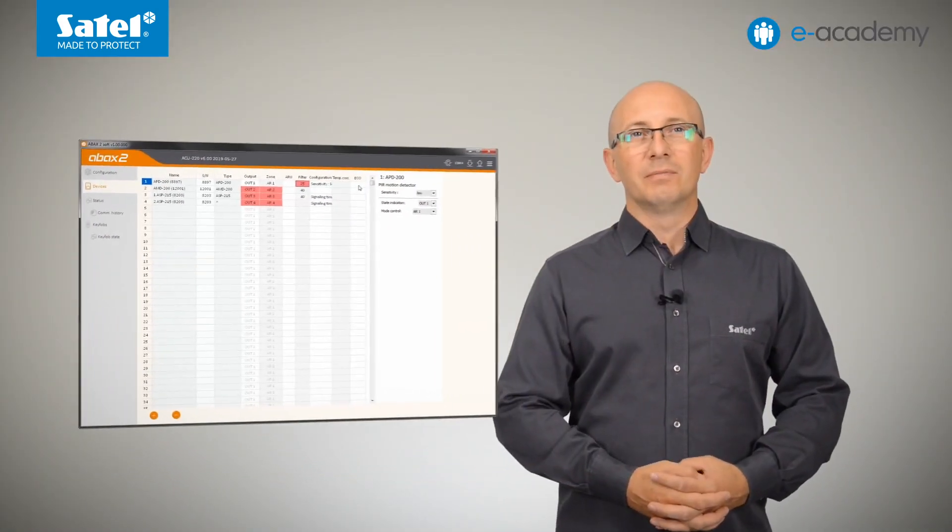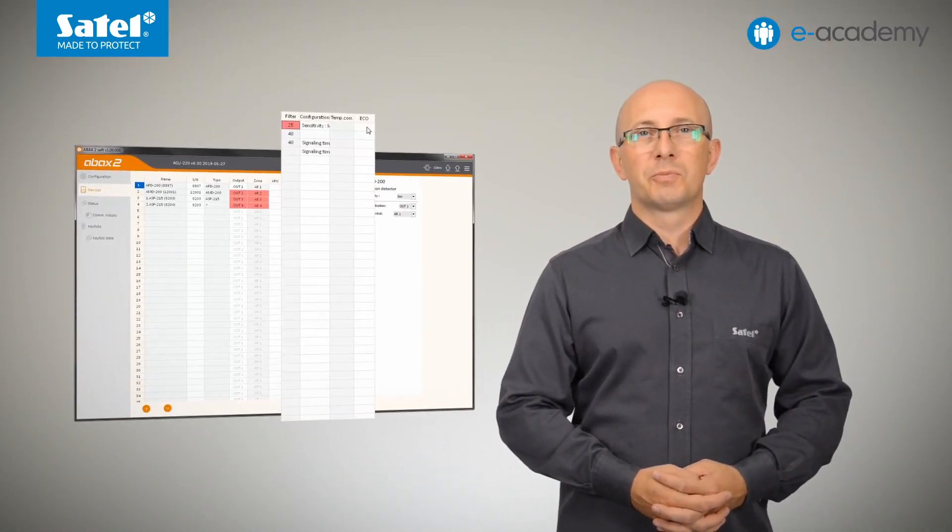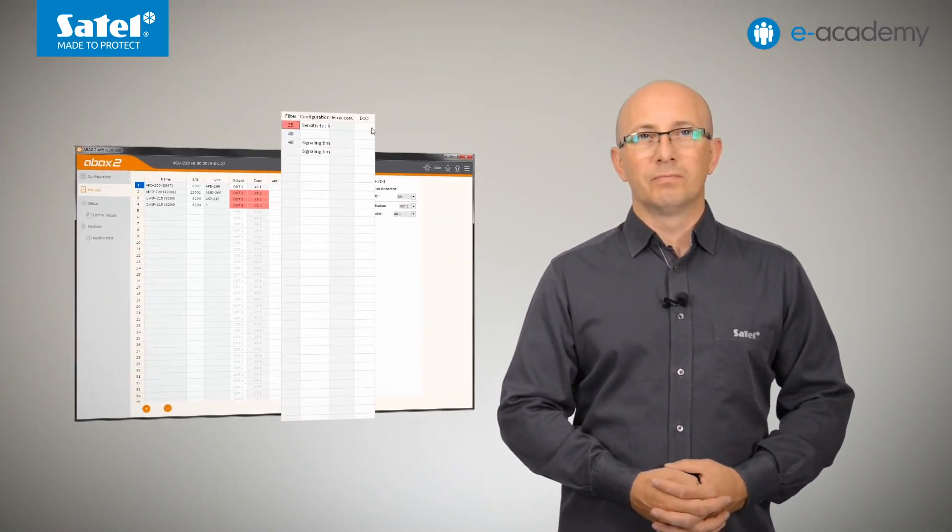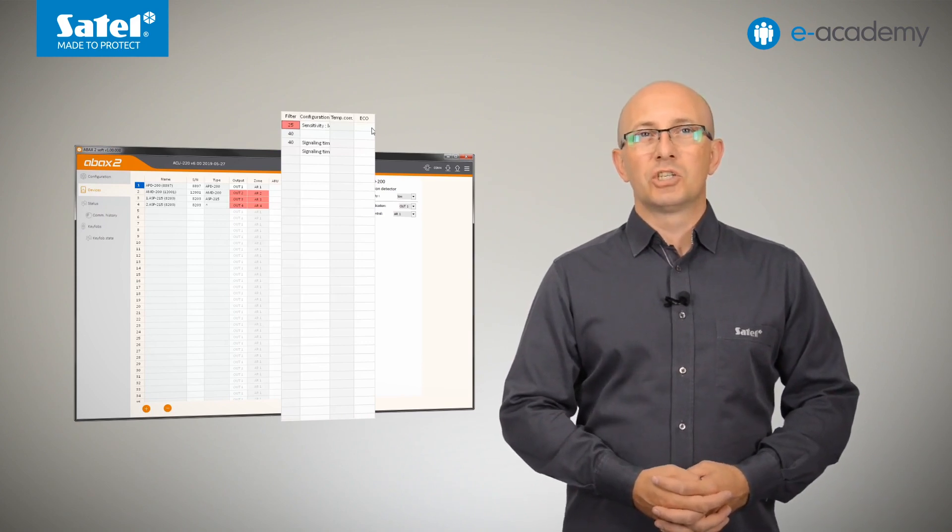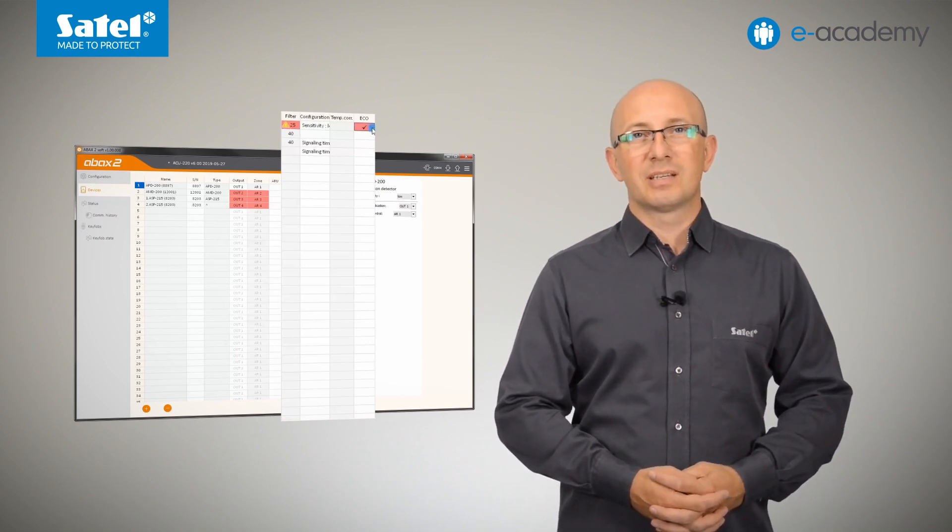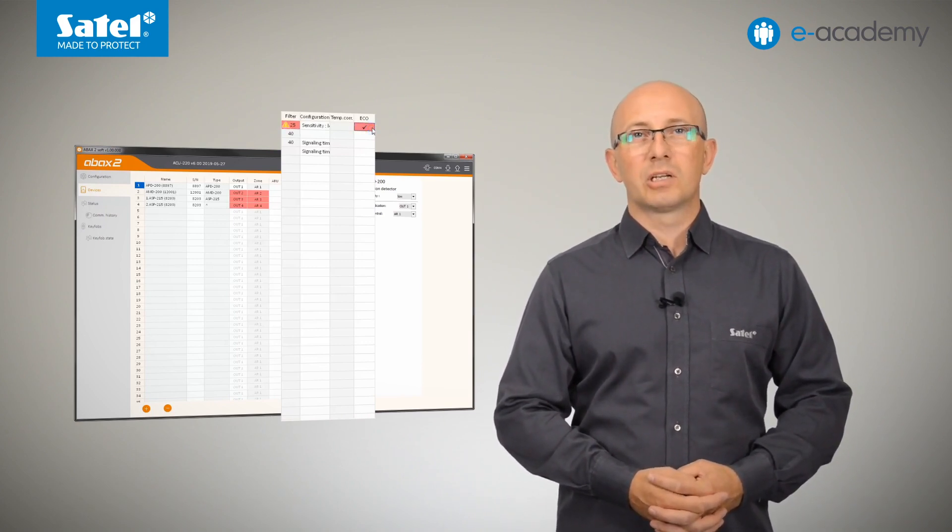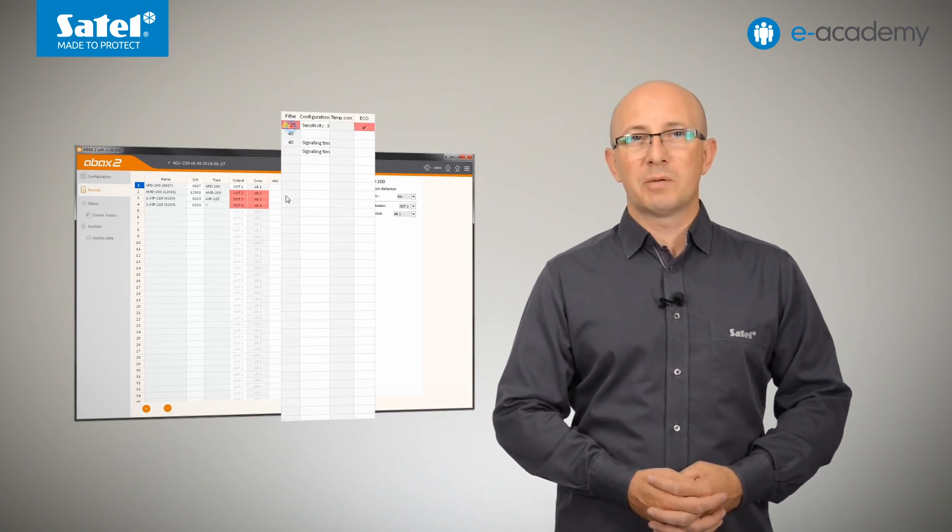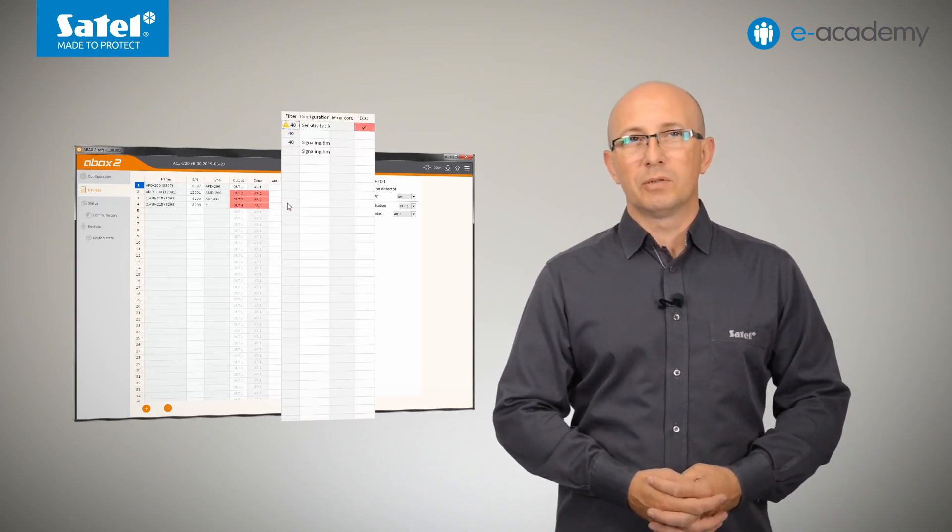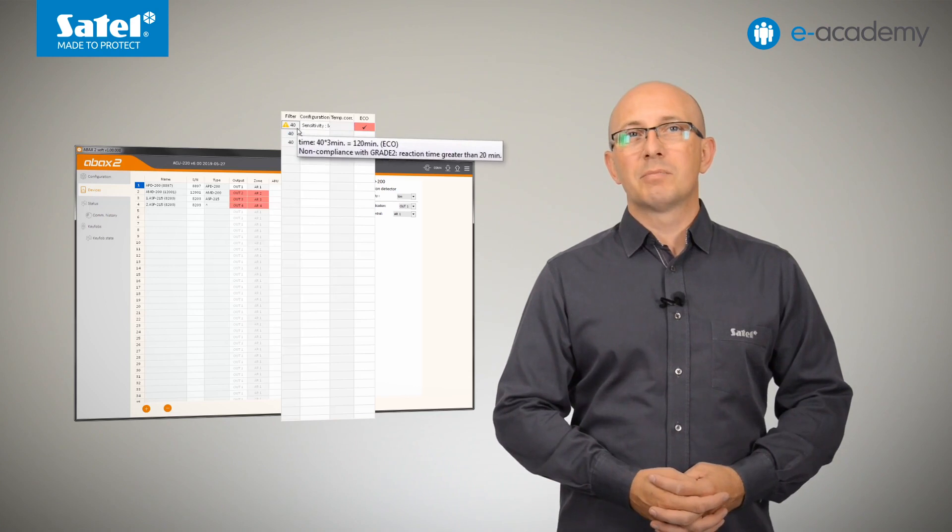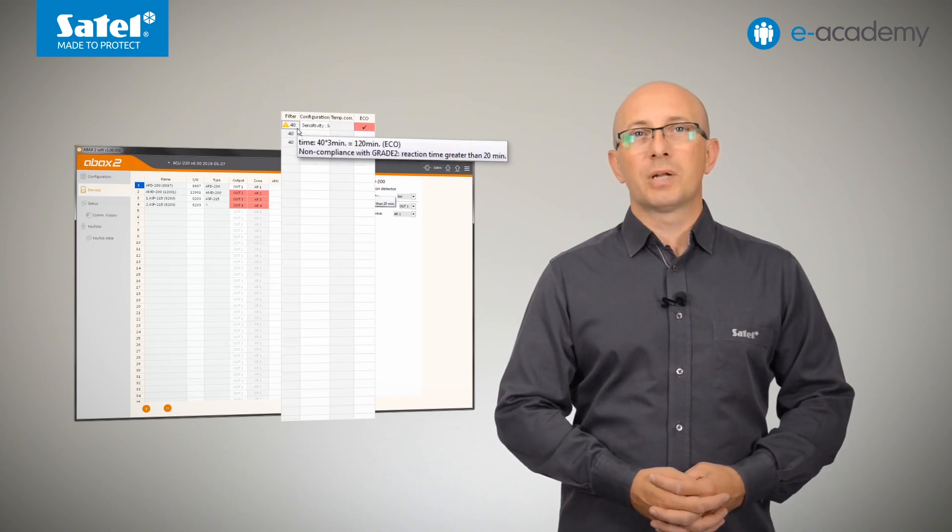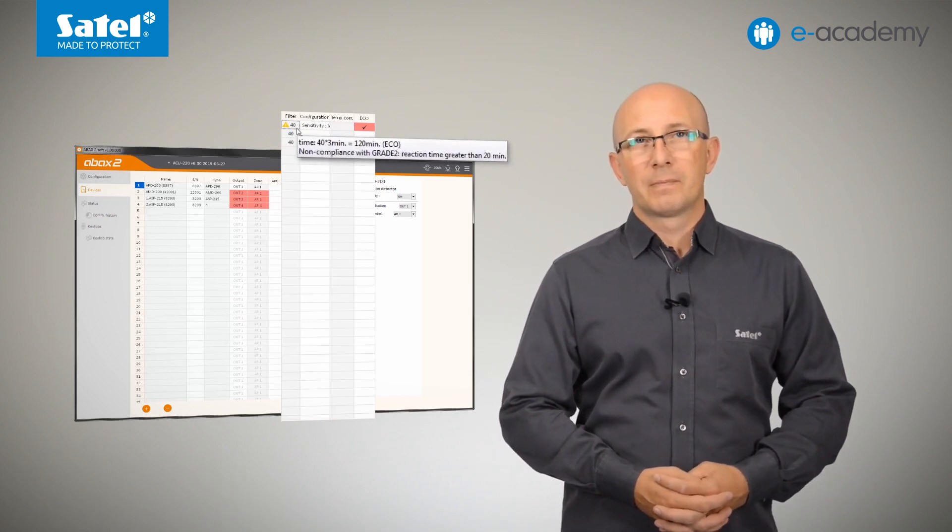Important note, in the last column, you can enable the Eco option. Please note that if the option is enabled for the selected radio device, then the periodic communication with this device will take place every 3 minutes. This significantly extends the maximum operating time without battery replacement.